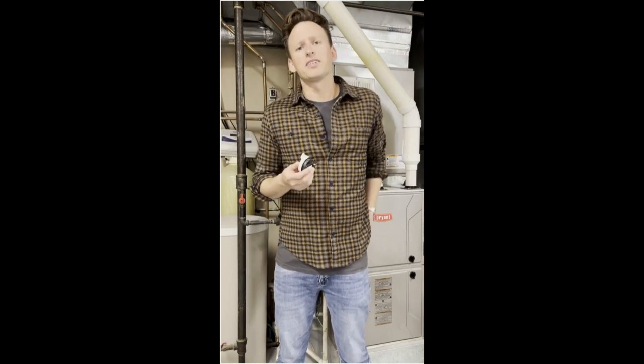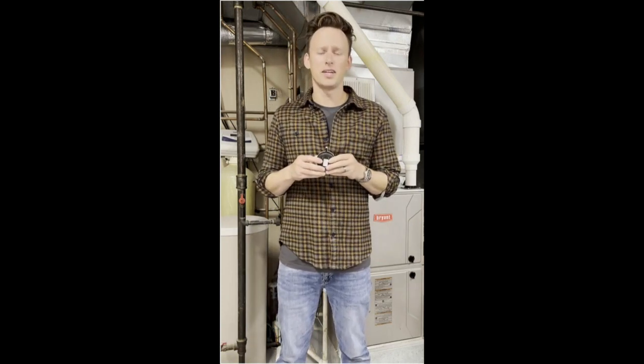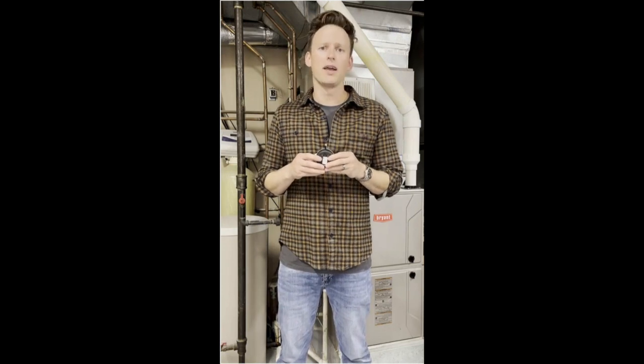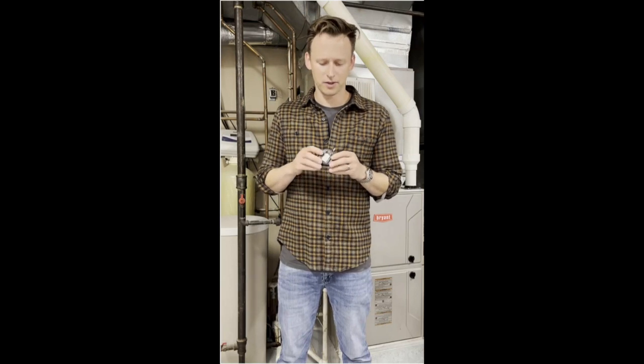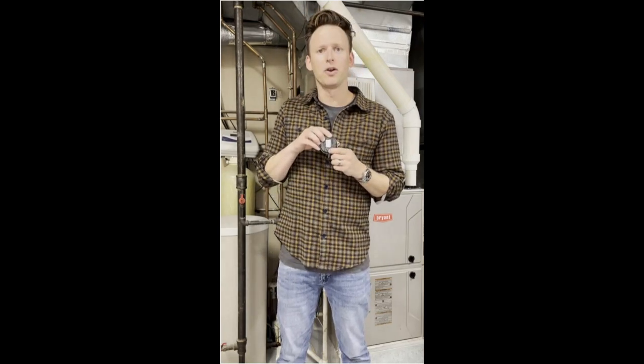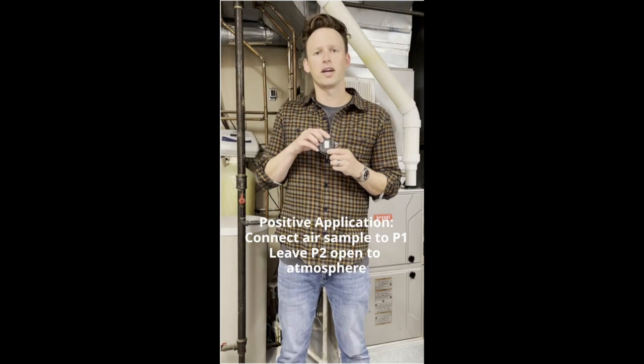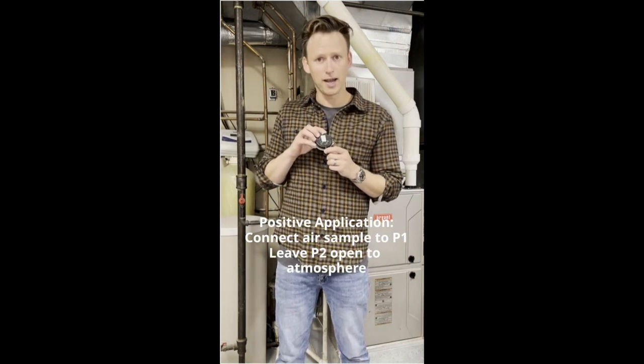Again, it covers anywhere from one-tenth of an inch to 10 inches of water column for positive, negative, or differential applications. If we have a positive application, we're going to connect our air sample connection to P1 or the black connection.